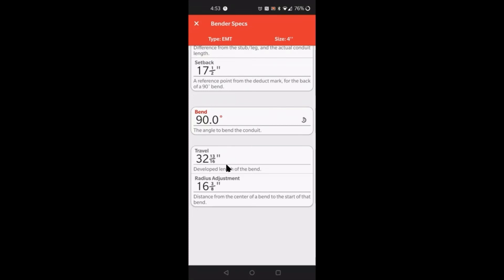But where you started off at, you still have a mark there as well. So as your mark is moving forward, once it gets to the value of 32 and 13/16 inches apart from the first mark that you started from, you have a complete 90. But this does not take into account spring back, so you do have to bend a little bit past to account for that spring back. Lastly, the radius adjustment is simply half of the travel. It simply is from the start of the bend to the center of that 90 degree bend, 16 and 3/8.